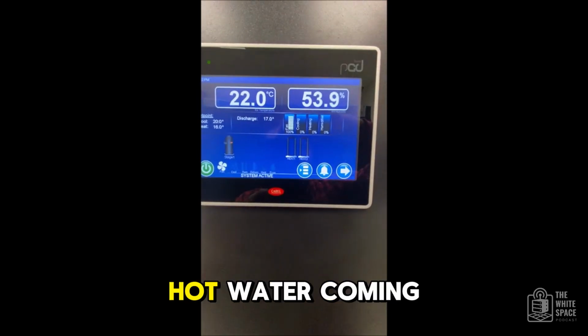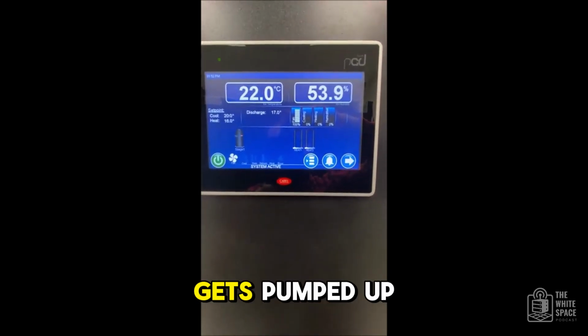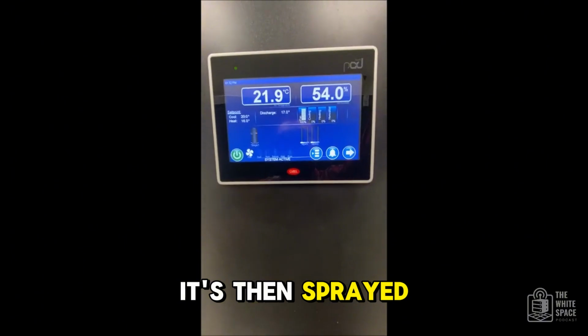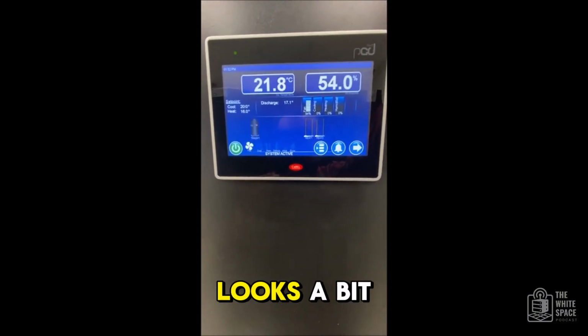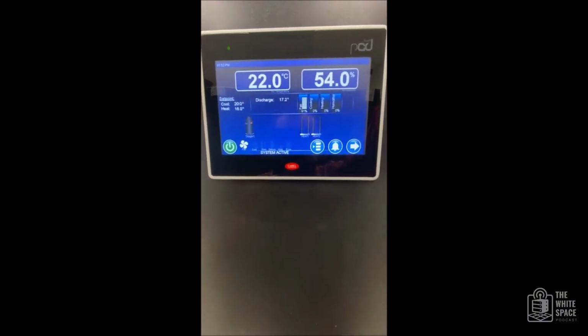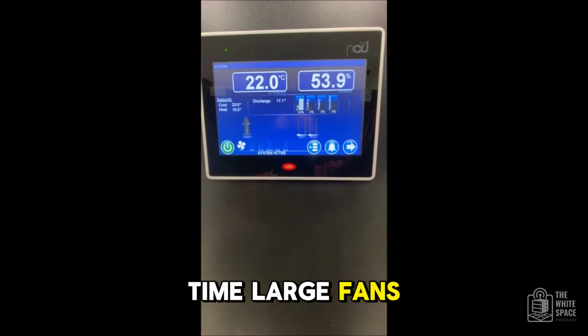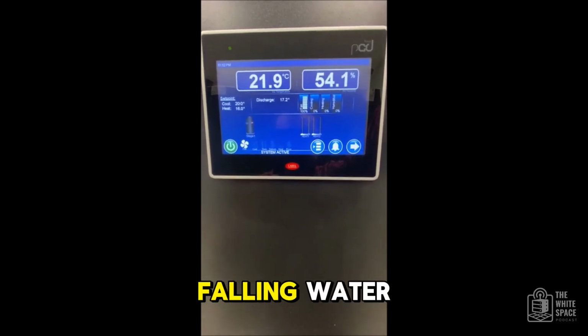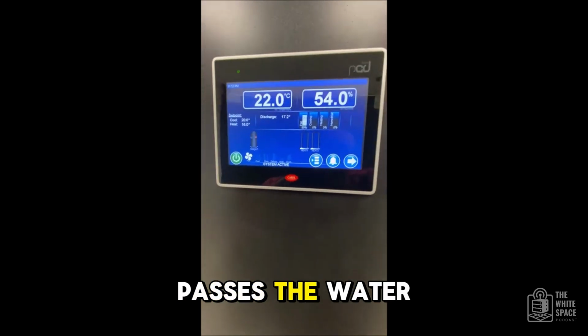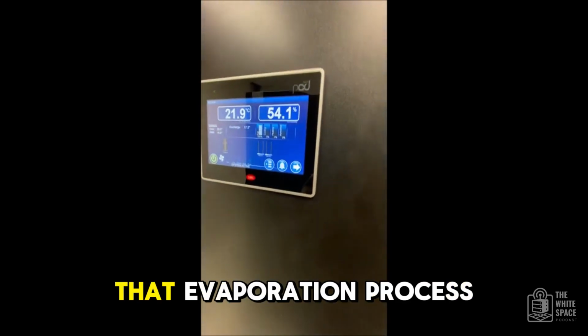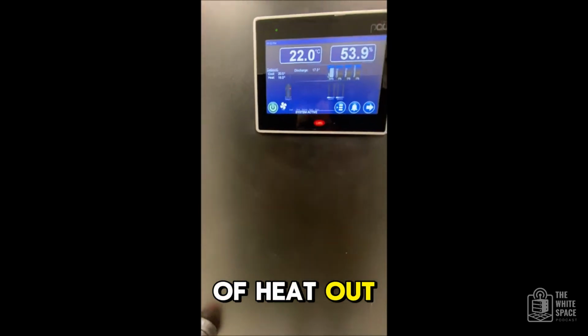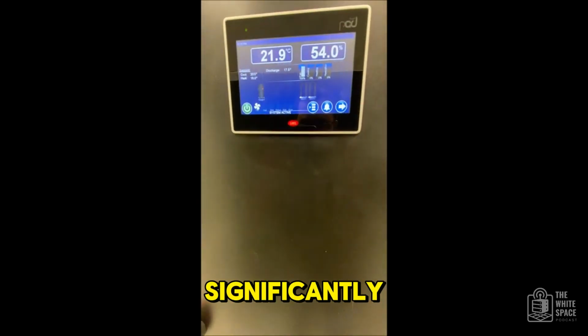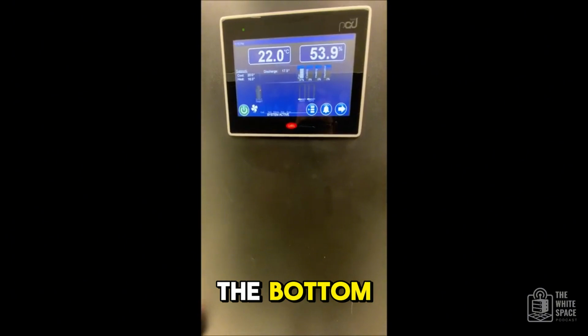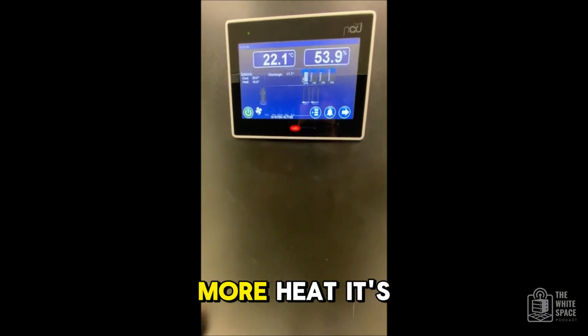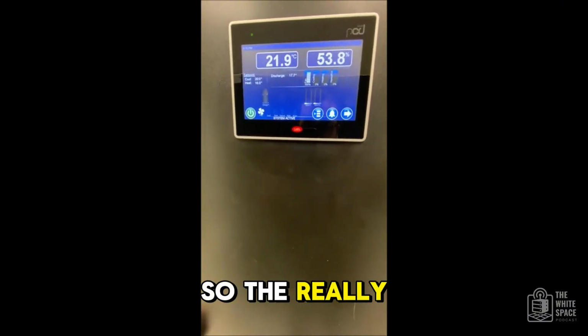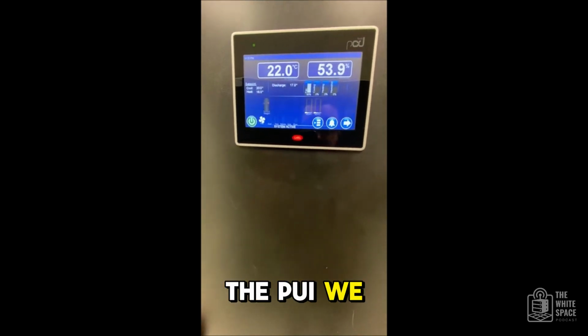It's pretty clever. Hot water coming back from the data center gets pumped up to the tower. It's then sprayed down over a material called fill. Looks a bit like honeycomb plastic sheets. At the same time, large fans draw ambient air up through this falling water. As the air passes the water, some water evaporates. That evaporation process pulls a lot of heat out of the remaining water, cooling it down significantly. That now cooled water collects at the bottom and gets pumped back to the facility to pick up more heat. It's a continuous cycle. So they're really key for the overall efficiency, the PUE we talked about.